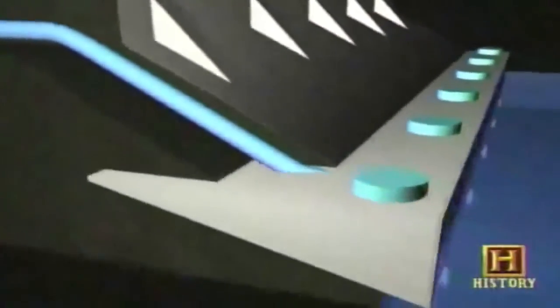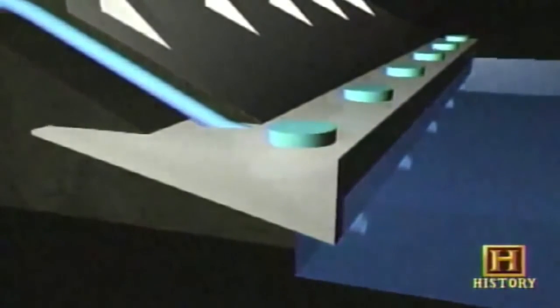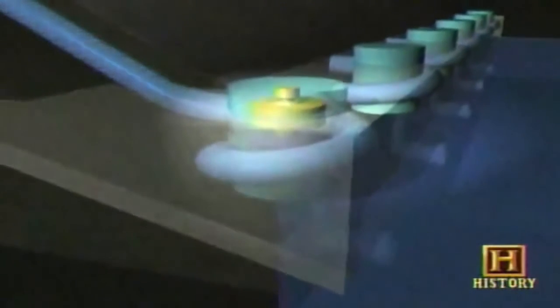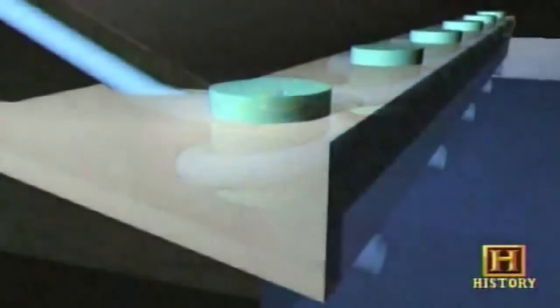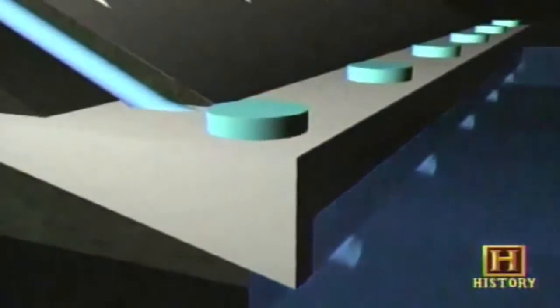Water enters the turbines. A shaft connects the turbine to a rotor, which is part of the generator. As the turbine spins below the generator, it turns the shaft and rotor. To produce electricity, the generator needs magnets and copper wiring. The magnets are affixed to the rotor's rim. The rim sits inside the stator, which surrounds the rotor with almost 400 copper coils. The rotor spins inside the stator, producing electricity in the copper coils.